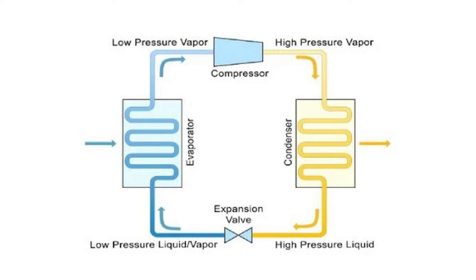Refrigerants are chosen specifically for their saturation temperature, which is commonly referred to as their boiling point, as this is effectively the temperature at which the refrigerant boils off in the evaporator, converting it to its vapor state before it re-enters the compressor. R134A, for example, has a saturation temperature of minus 26 degrees Celsius, and is used for medium temperature applications such as domestic refrigerators.